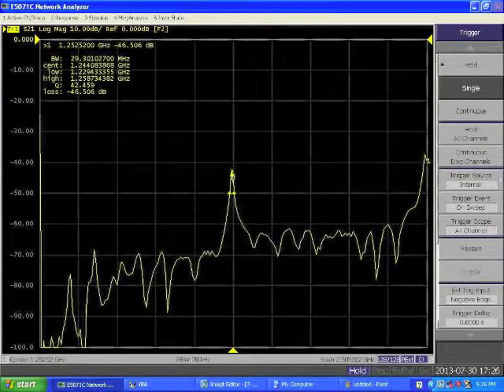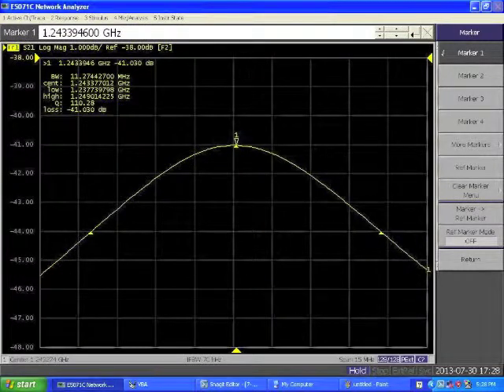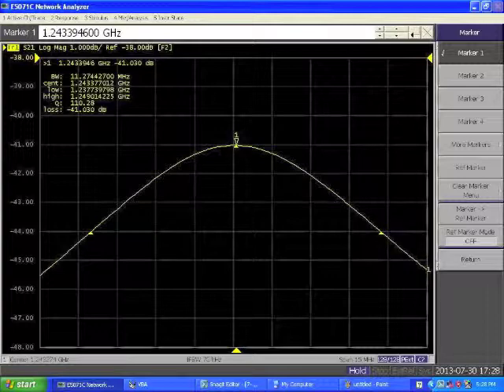Once we have the peaks identified, we're going to adjust the span and the scale to find the first peak at 1 GHz. Should always lie somewhere around 1 GHz. We're going to continue to narrow the span and adjust the scale so that we fill the network analyzer screen with the resonance peak. Then we use the marker functions on our network analyzer to measure the center frequency and the Q. On our network analyzer, this is the bandwidth marker functions, and it measures the Q and the center frequency, which is going to be the input to the calculator software to measure decay.